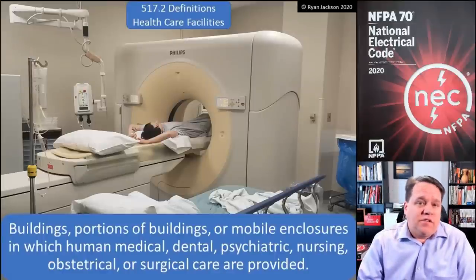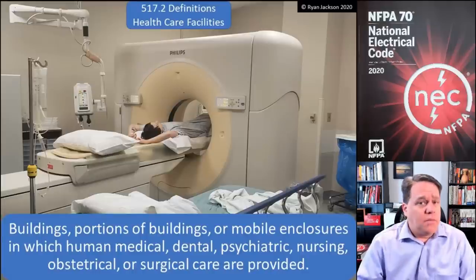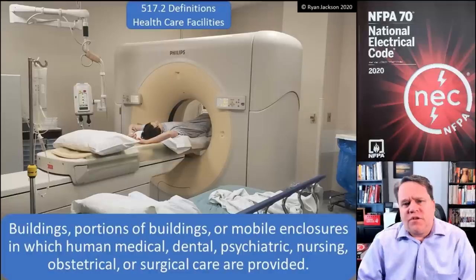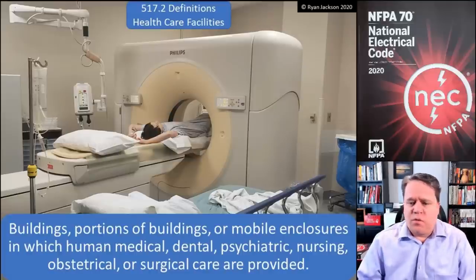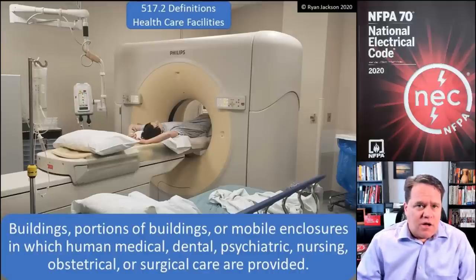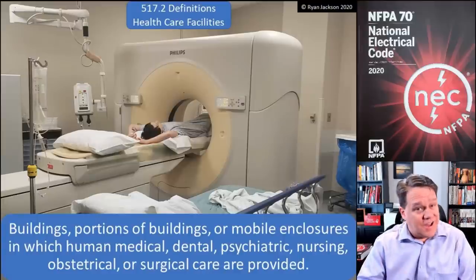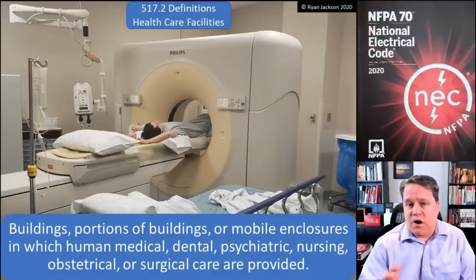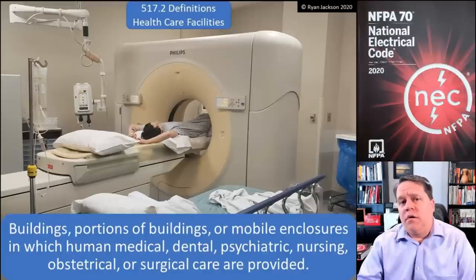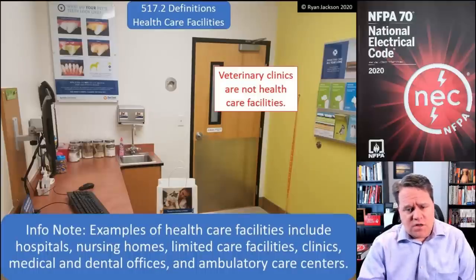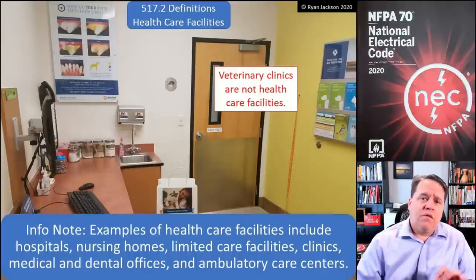517.2 tells us that a health care facility is a building or a portion of a building, or even a mobile enclosure, in which human medical, dental, psychiatric, nursing, obstetrical, or surgical care are provided. So a health care facility is pretty much what you think it would be — somewhere there are doctors and nurses, dental, psychiatric care. Some types of care covered might not jump into your mind immediately, like psychiatric care. They also mention in the scope and definition that this is only for humans.